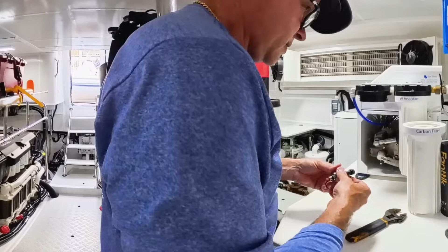Perfect, it's 0 to 2,000 PSI. This one they gave me is a little different. That being said, let's put a little thread sealant on here even though it's got an O-ring, and then we'll get some dielectric grease and put it in there so we don't have a corrosion problem again. Hopefully this solves my problem. I'm hopeful I don't have to change the cable because that would be harder work. So snug that down a little, not too much because it has an O-ring. Grease, oh the super lube. Chris loves the super lube.